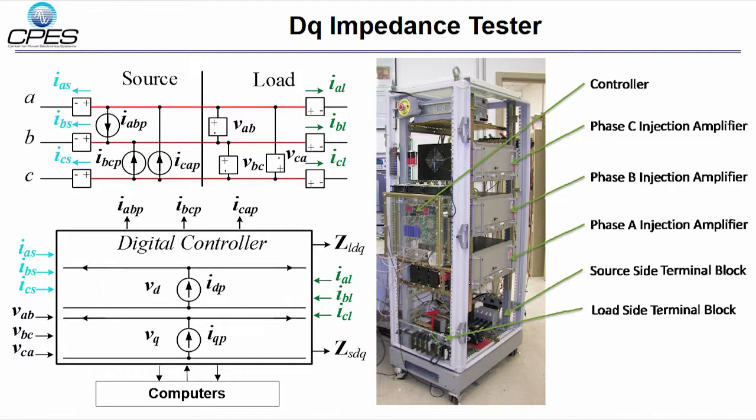ABC frame perturbation signals are amplified by the power amplifiers and then applied to the system to be tested. Voltage and current response from the system are collected and transferred to DQ frame by the digital controller. Impedances are calculated by the computer using response signals and perturbation signals.